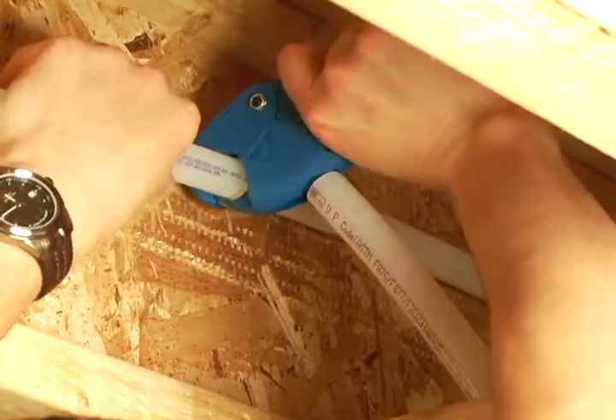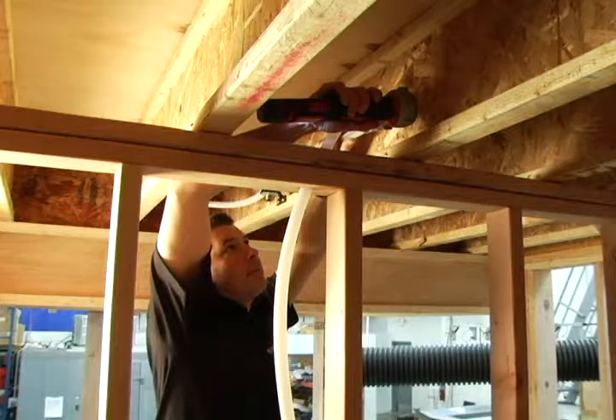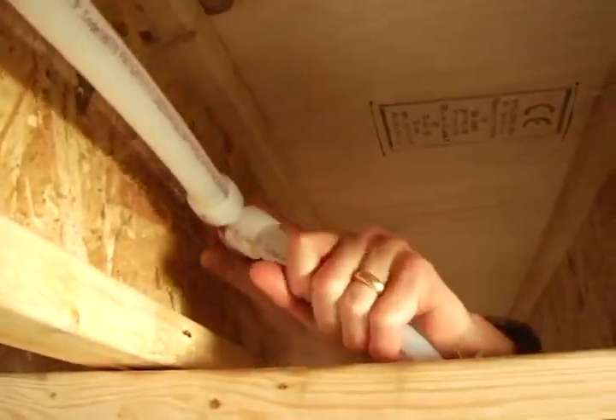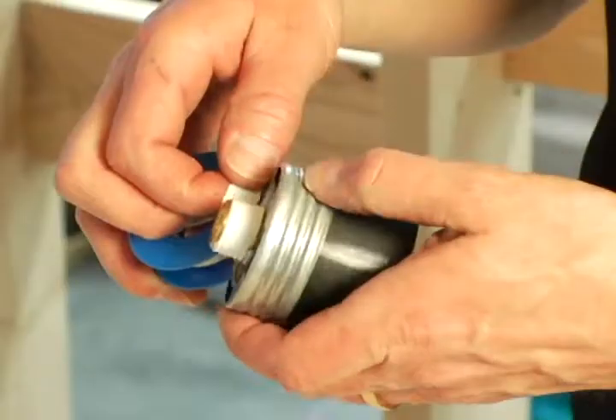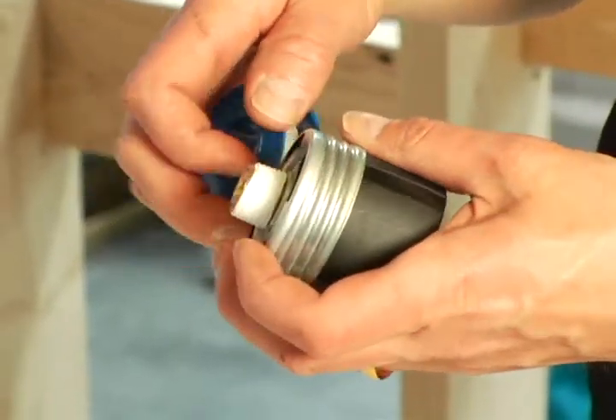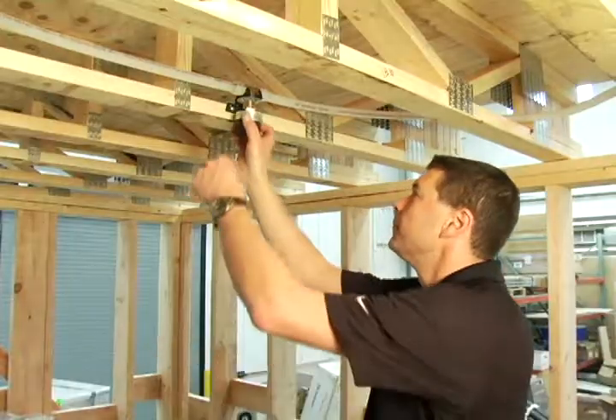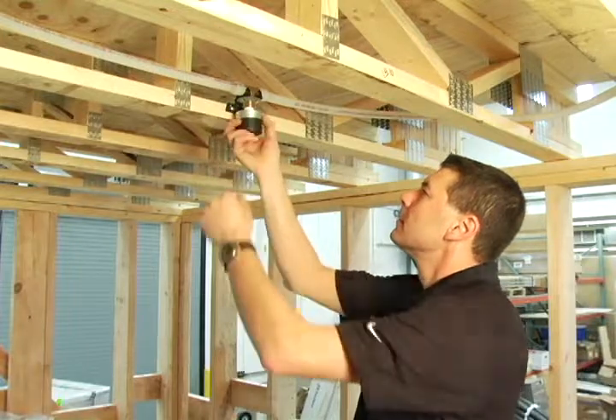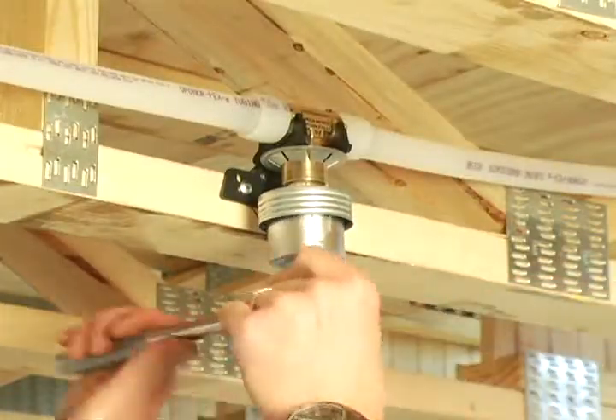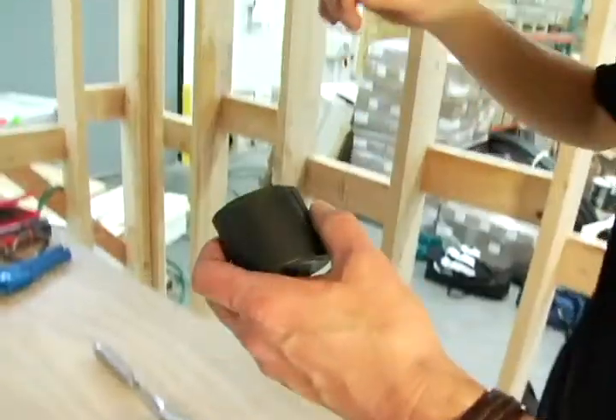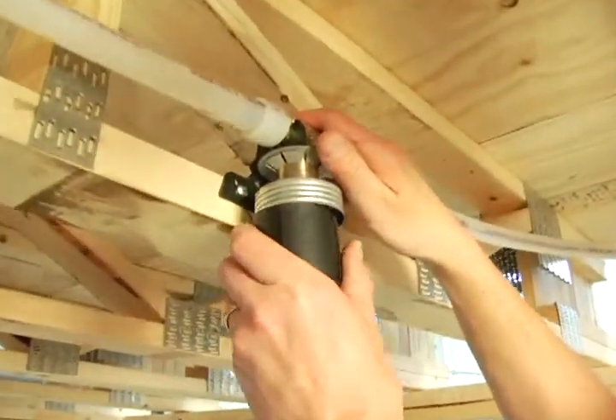Next, cut into the sprinkler line. Then, insert a brass drop-down tee using the same Propex connection method. Now you can connect the plumbing system to the sprinkler drop-down tee. We're now ready to attach the sprinkler to the sprinkler adapters. Thread the sprinklers into the adapter, then carefully tighten 1 to 2 full rotations. Be sure to protect the sprinkler with the cover when you're done.